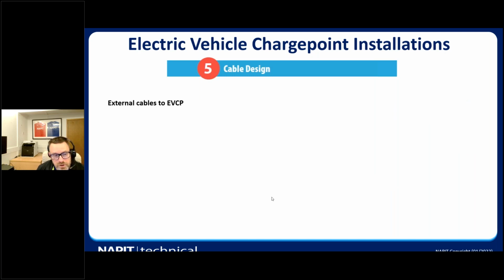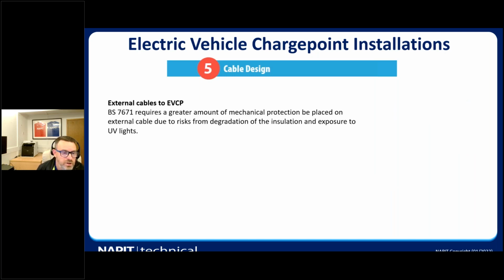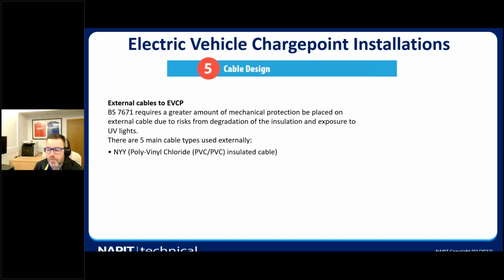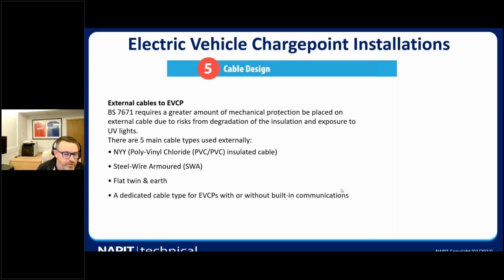And external cables to the EV charge points. We're looking at a greater amount of mechanical protection placed on the cables because of degradation from exposure to UV light, because they're outside all the time. And the 5 main cables used externally are the NYY polyvinyl chloride cable, steel armour cables, flat twin earth, dedicated type for EV charge points, and singles installed in conduit trunking.